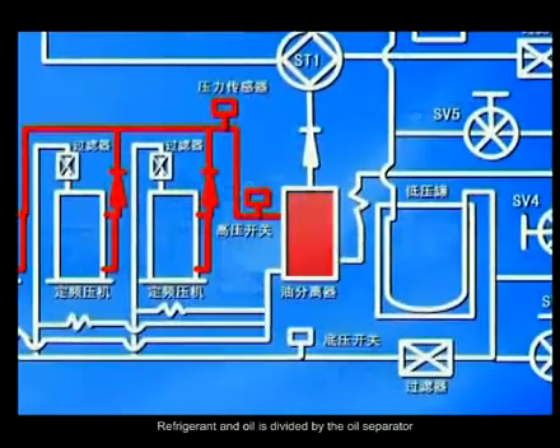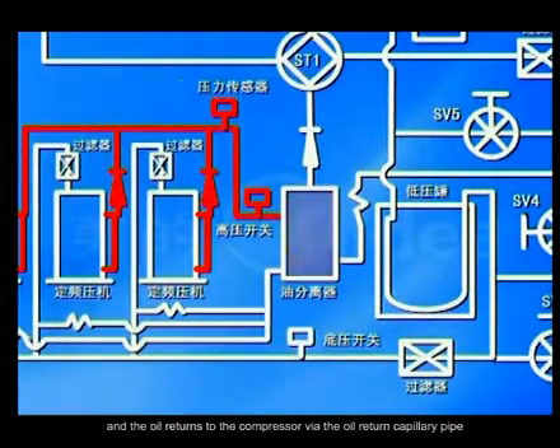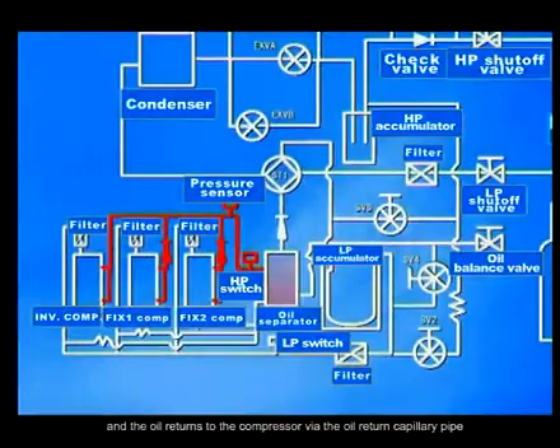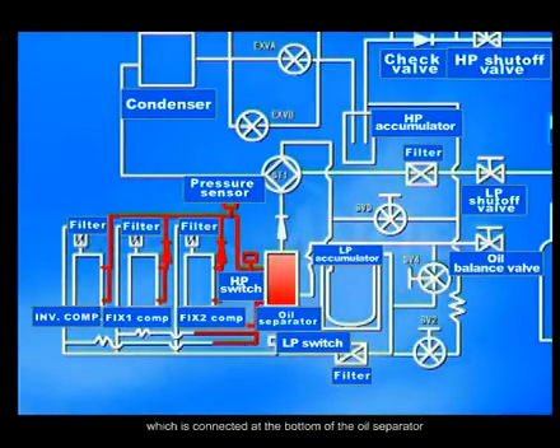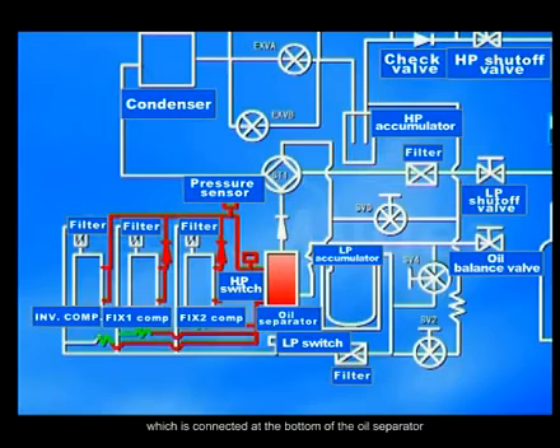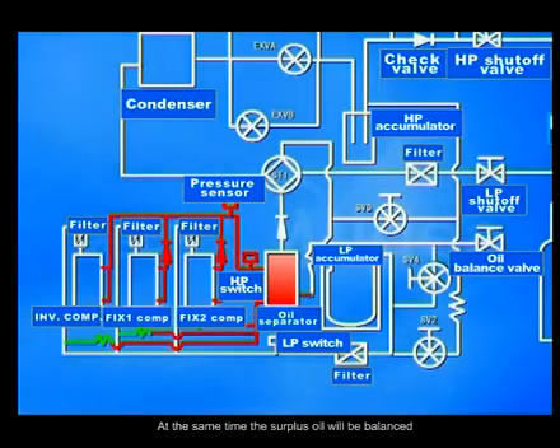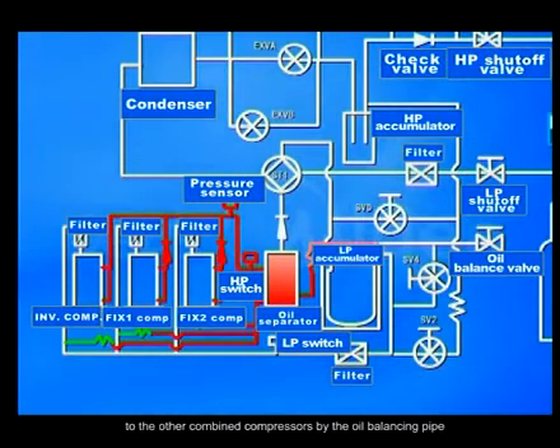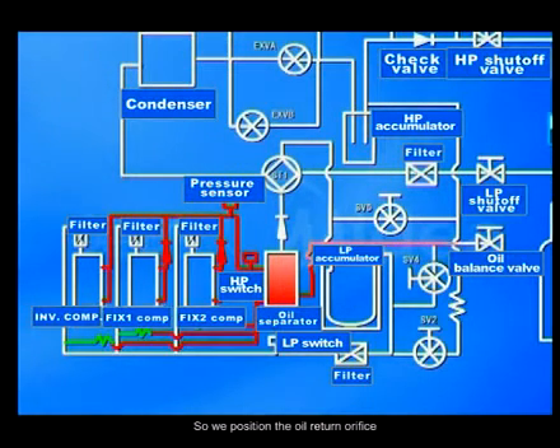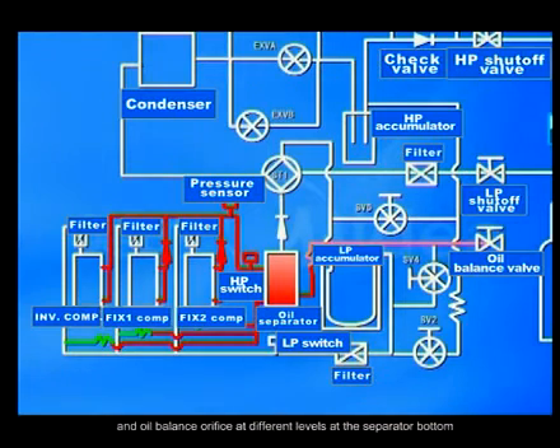Refrigerant and oil is divided by the oil separator, and the oil returns to the compressor via the oil return capillary pipe, which is connected at the bottom of the oil separator. At the same time, the surplus oil will be balanced to the other combined compressors by the oil balancing pipe. So we position the oil return orifice and oil balance orifice at the different levels at the separator bottom.